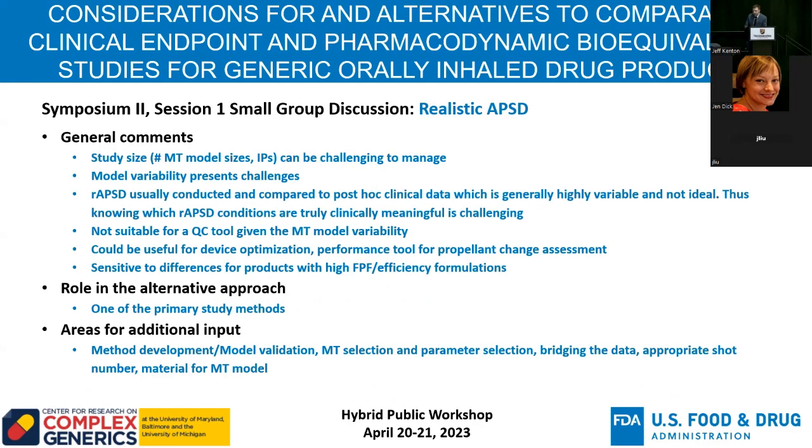So we had a discussion on realistic APSD, and some general comments across that were certainly the challenges that can come from the study size. So again, the number of mouth-throat models and inhalation profiles. If you're trying to do a wide-ranging study, this creates a lot of NGI studies that you'd have to do, so that's certainly challenging. The variability of the models themselves can also present challenges.